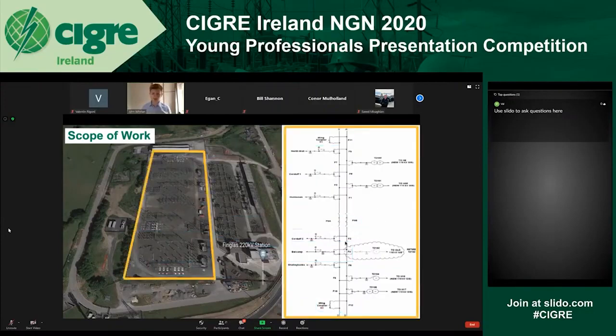Electrically, a new Toshiba GRB 100 busbar protection scheme is to be installed to cater for all 14 bays. The 5 new bays will go straight into that scheme, and the 9 existing bays will be transferred into it. All of this work is to increase the security of supply at Finglas, increase flexibility, and crucially, the connection to Belcamp is allowing for the connection of a large data center at Belcamp station, which is the sole feeder to that substation.